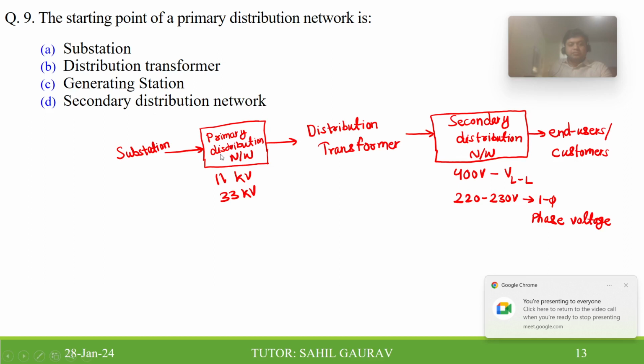Yeah, Manish is typing A. Yes, A option is correct. We have the substation first, then the primary distribution network. This connects the substation to the distribution transformer, and then we have the secondary distribution network that connects distribution transformers to individual customers. Generally in India, the primary distribution network has a voltage of 11 kV or 33 kV, and the secondary distribution network has 400 volt, that is line to line voltage, and if you convert into phase voltage, it comes to 230 volt.